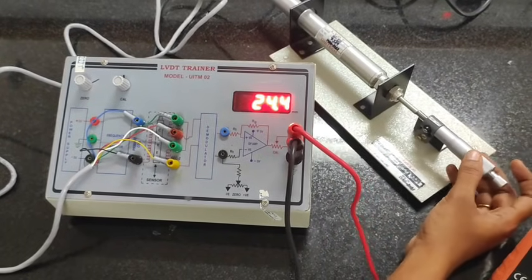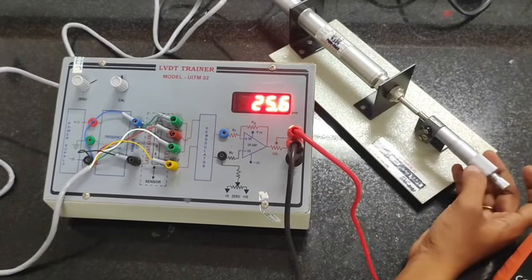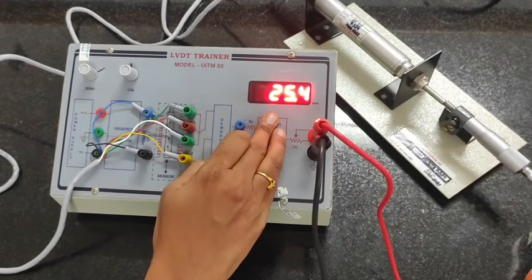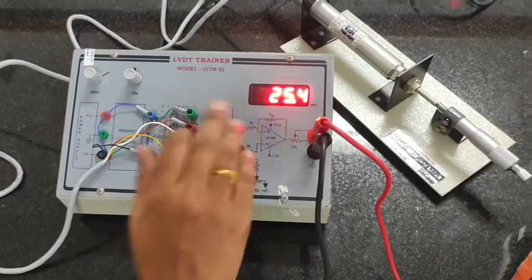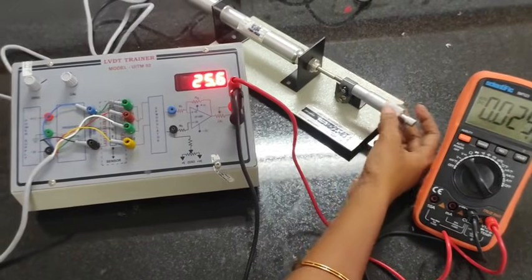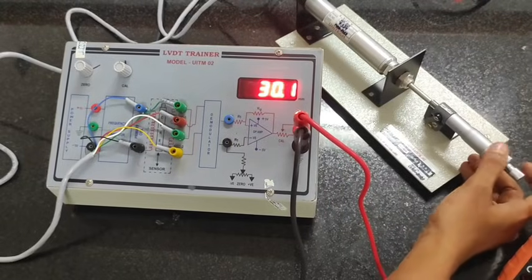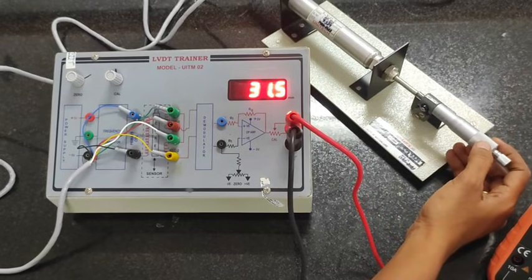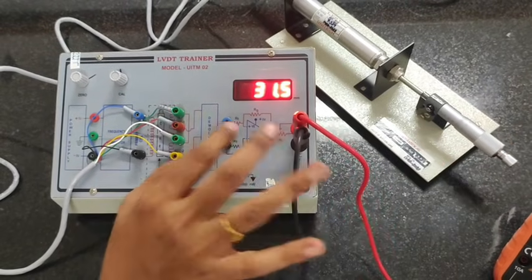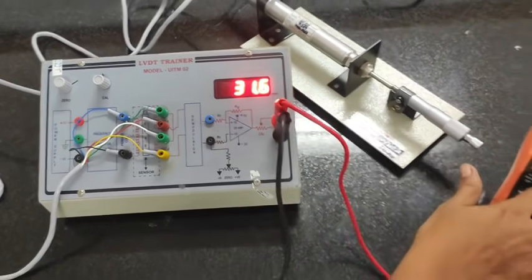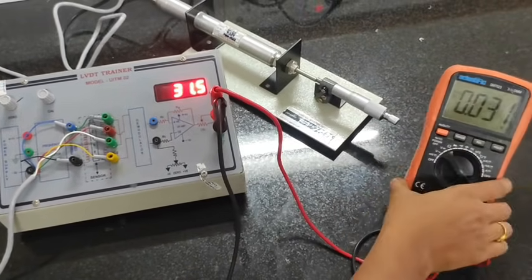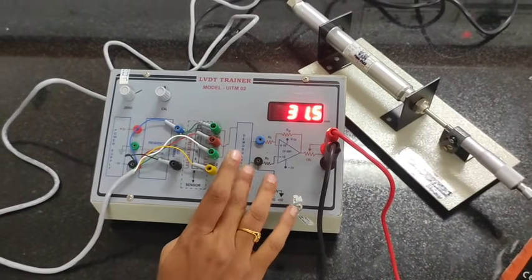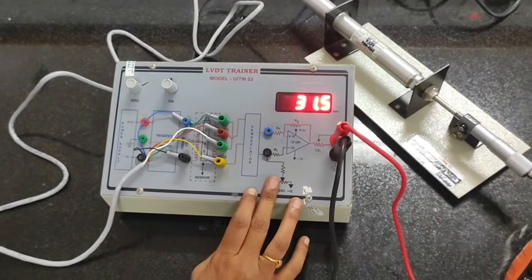Then we can start taking readings for both positive displacement and negative displacement. From keeping the center as position 10, you can take readings like 10, 12, 14, 16, 18, 20 for positive displacement. And similarly, you can take readings for 2, 4, 6, 8, 10 for negative displacement. And you can calculate the error for the displacement and output voltage, comparing the displacement in the screw gauge and the displayed displacement.